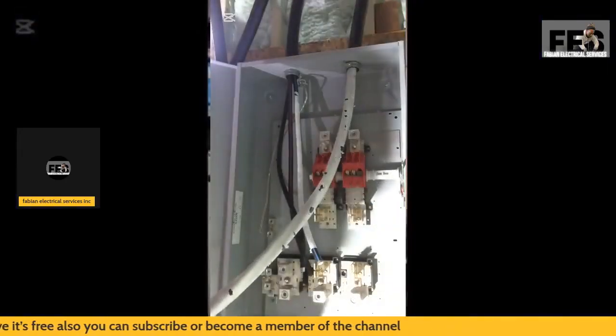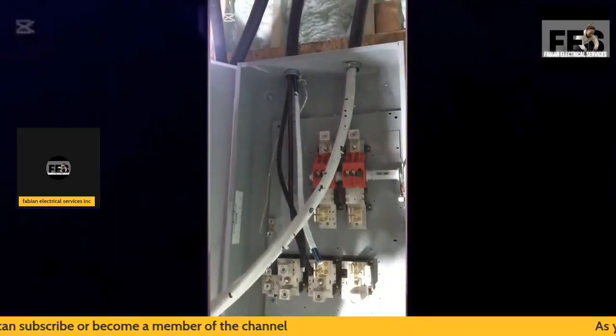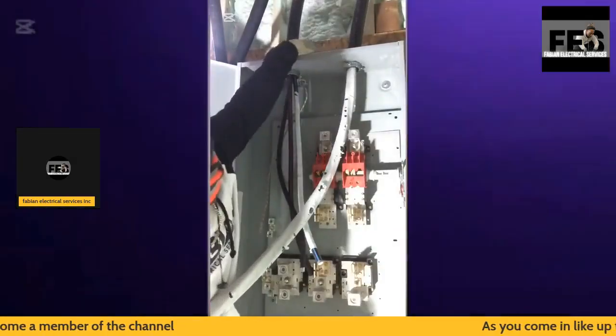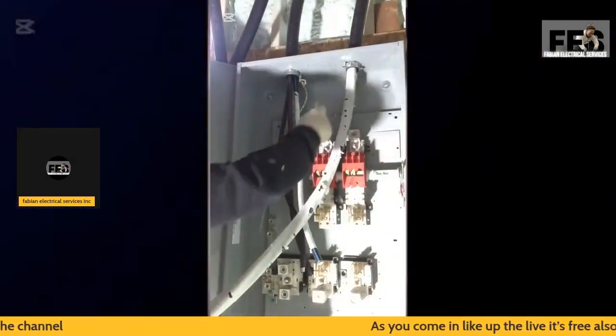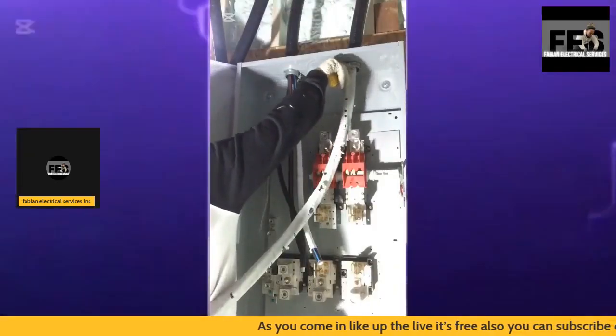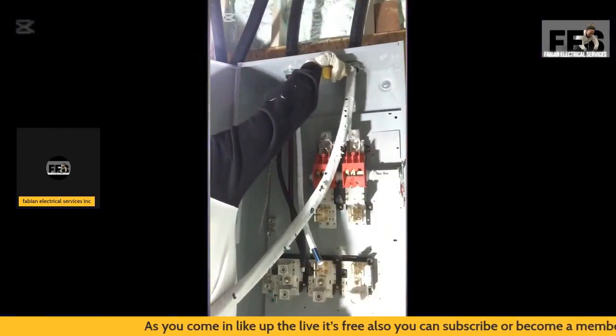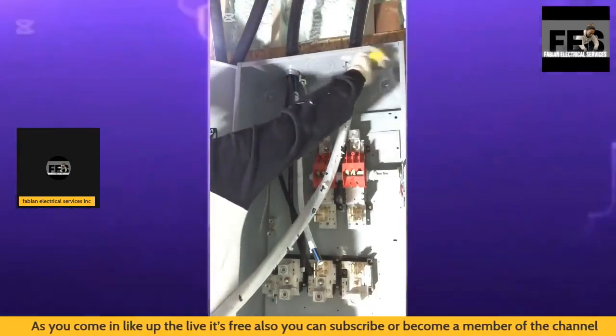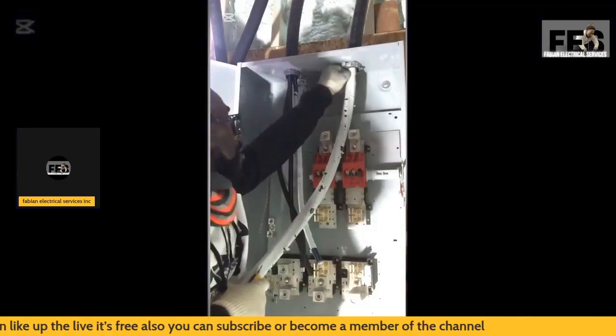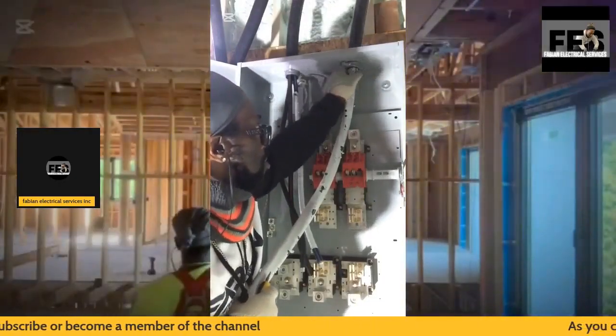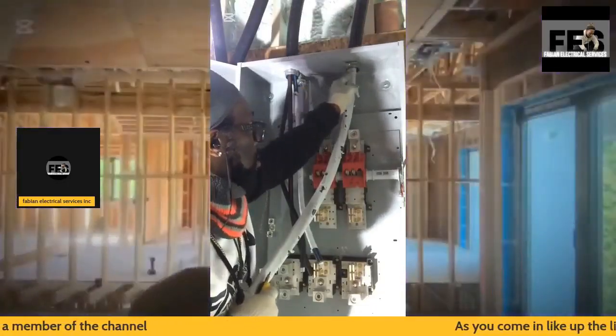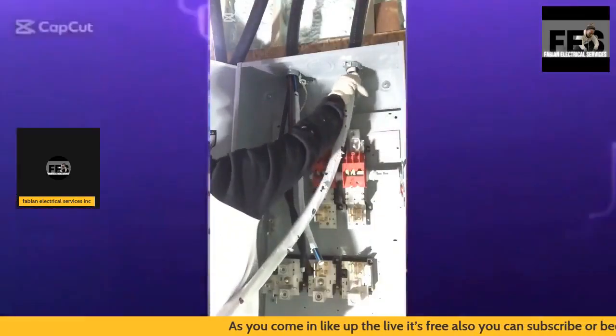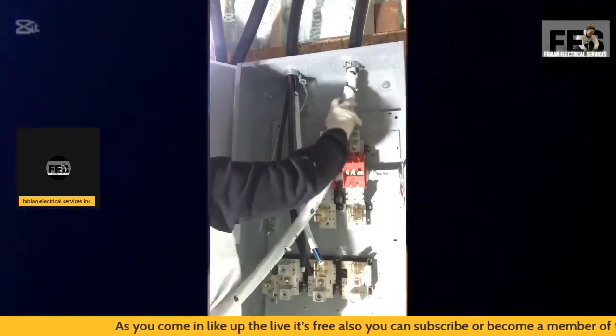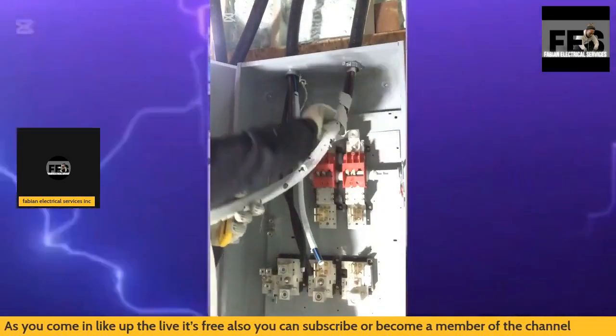So the reason the disconnect is here and not the 400 amp panel is because of the code rule that states anything within 5 feet of the meter base shall have an installation of the panel right away. But when it comes to any electrical installation that's more than 5 feet away from the actual electrical disconnect located outside of the home, it has to have a means of disconnect.